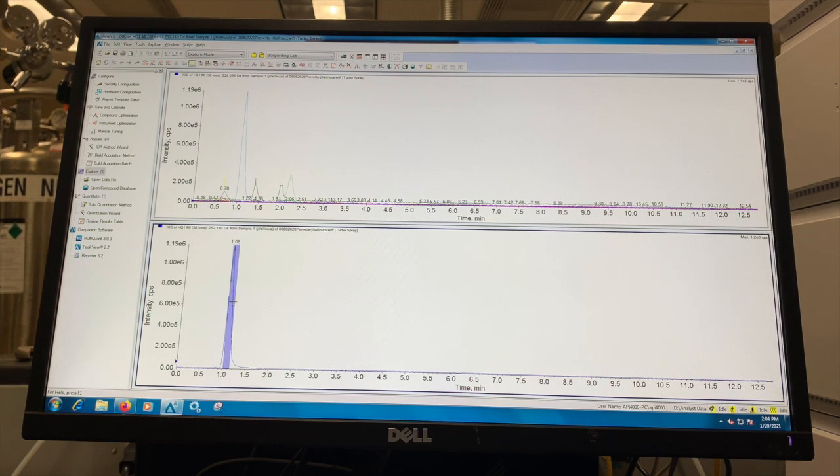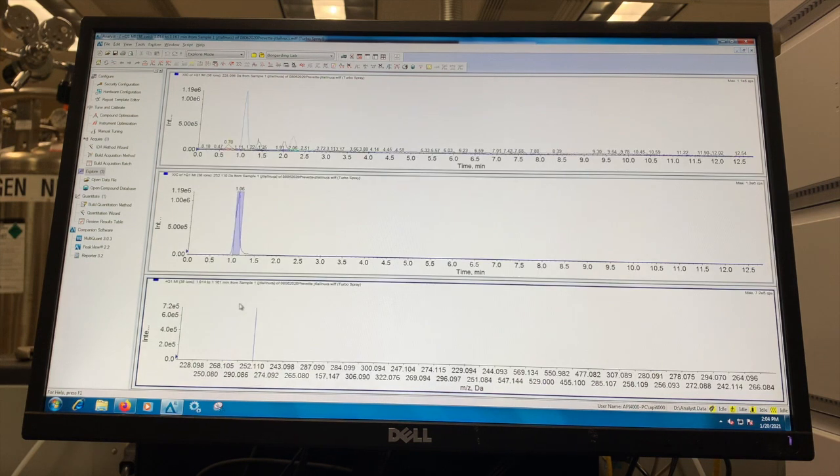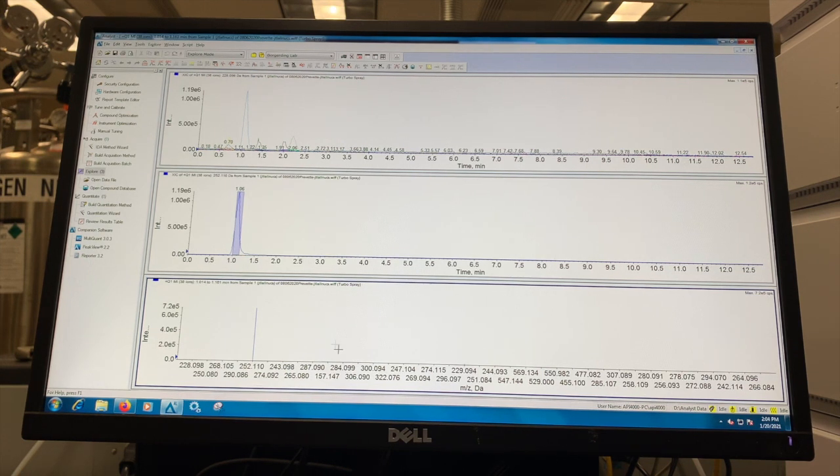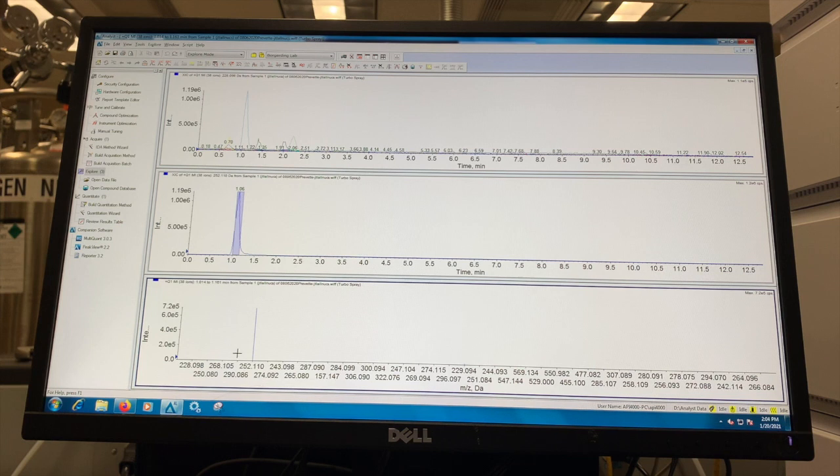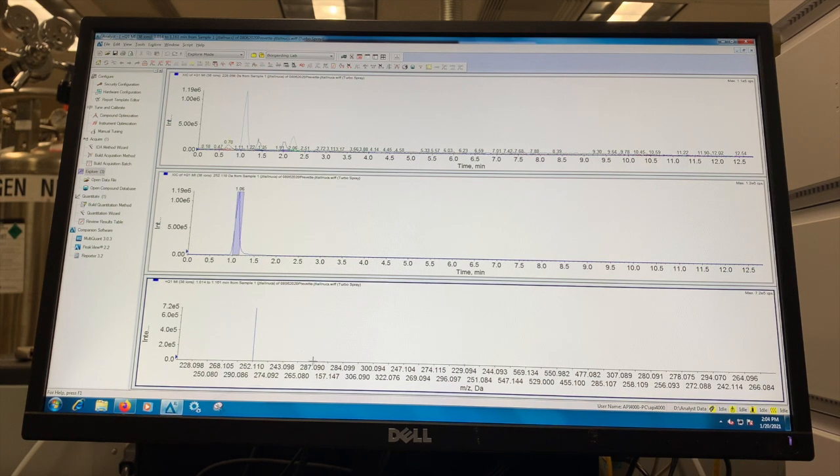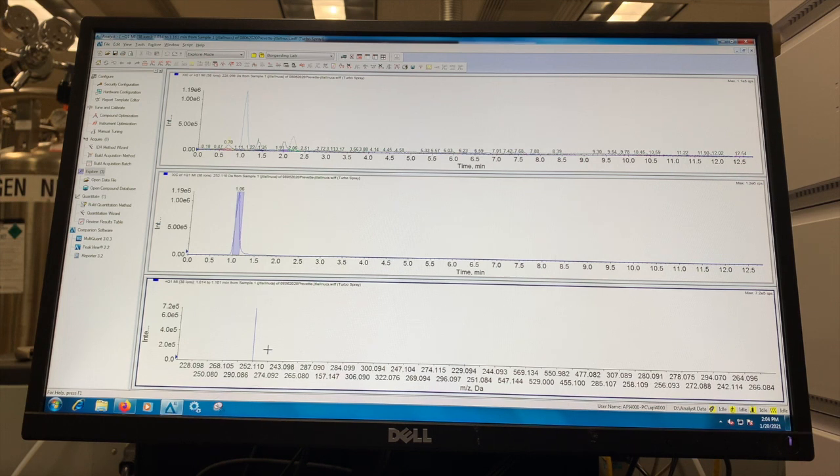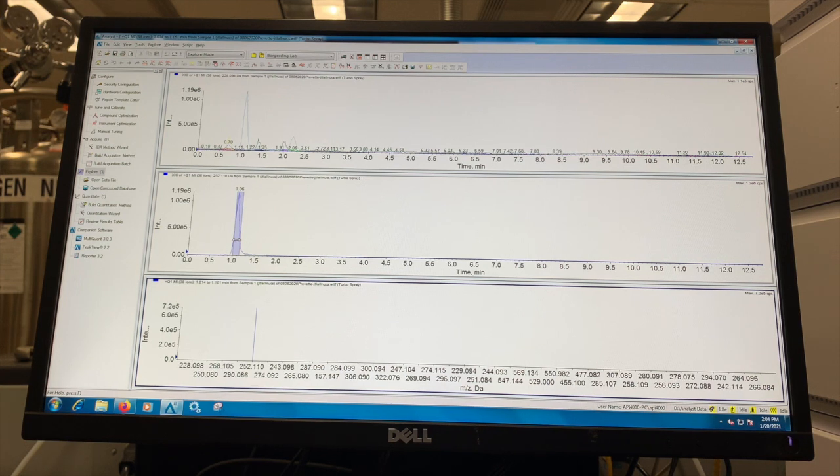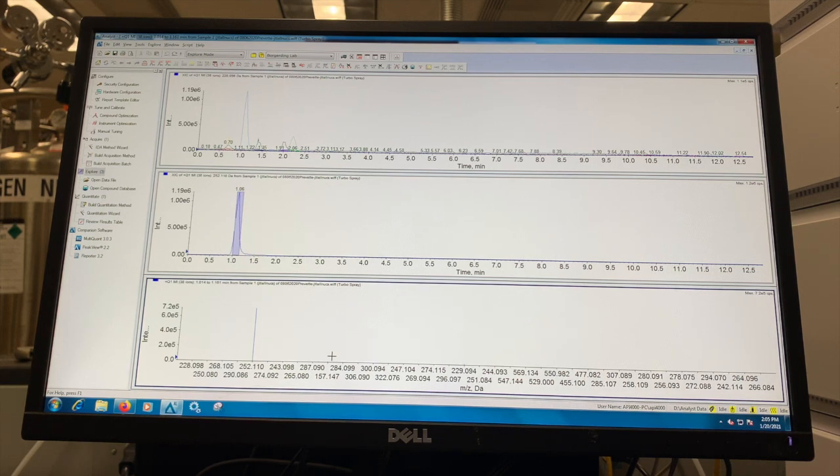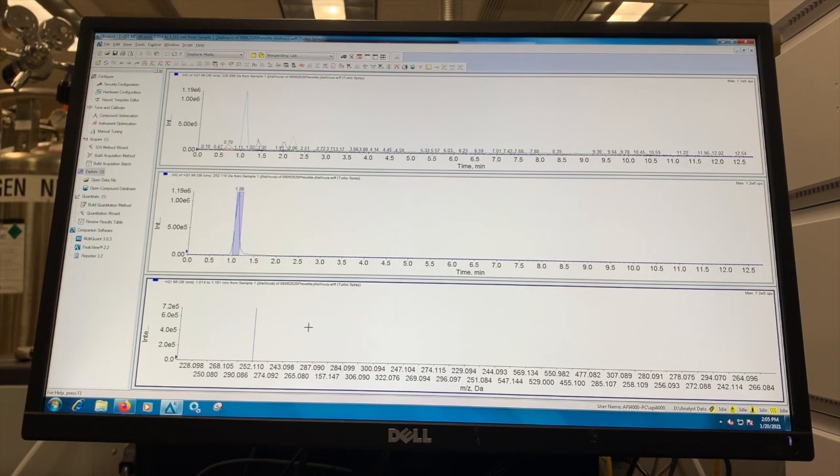Now, the main difference in the spectra of the selected ion mode chromatograms are that whereas in EMS mode, which is the total ion, we are scanning over a range of masses. Here, we only have the distinct separate masses. Now, this lowers the background noise of the whole method, which can lead to lower limits of detection. However, you only get really small snapshots of masses in a range rather than the full picture of every mass in a range. So there are benefits and drawbacks to this method.